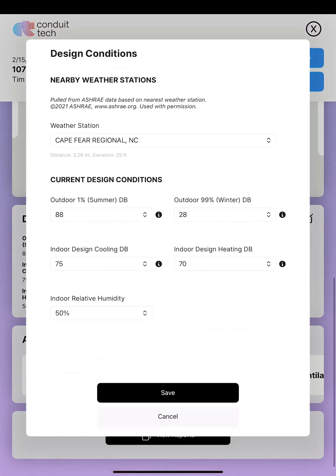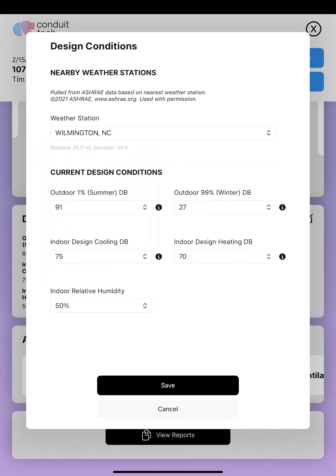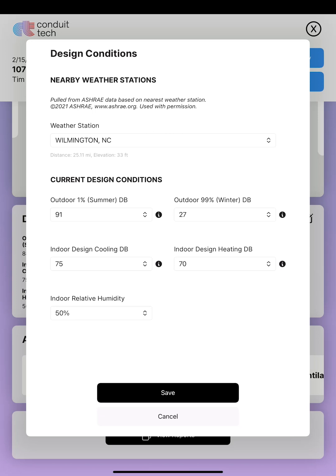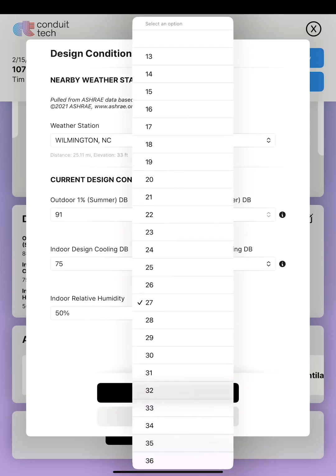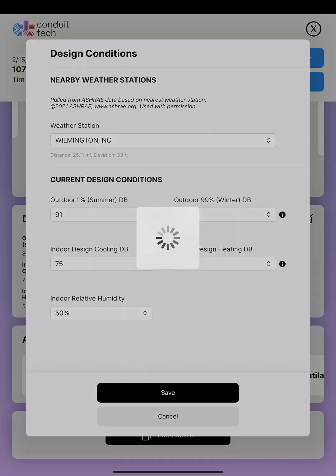The next thing is design conditions — another cool feature. Conduit Tech will choose the closest ASHRAE weather station to you, but you have the option to override it. Here it's choosing Cape Fear Regional, but that's right at the beach, with a completely different climate and humidity than I have a few miles inland. So I'm actually going to choose Wilmington, North Carolina because it more closely resembles my actual weather. You can also fine-tune your indoor and design conditions. The app does want us to acknowledge that this is an override, which is completely understandable.